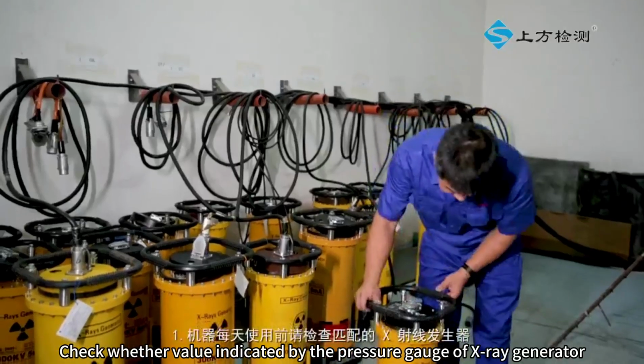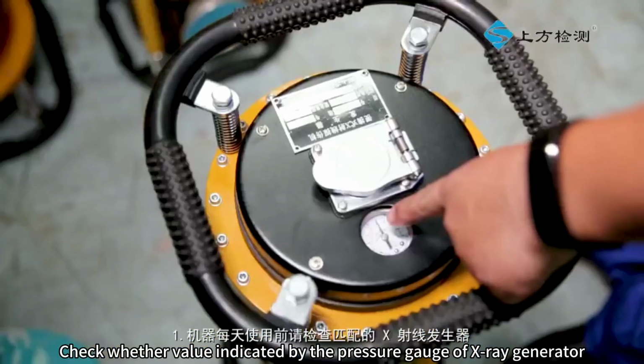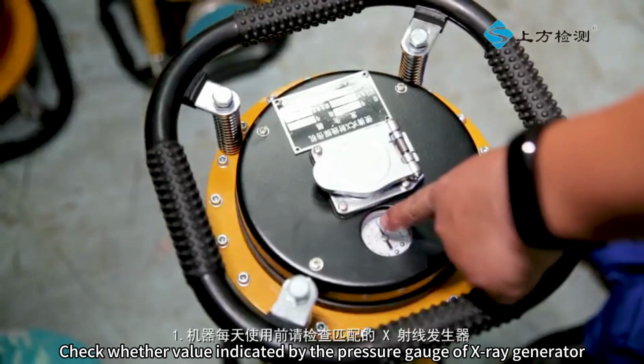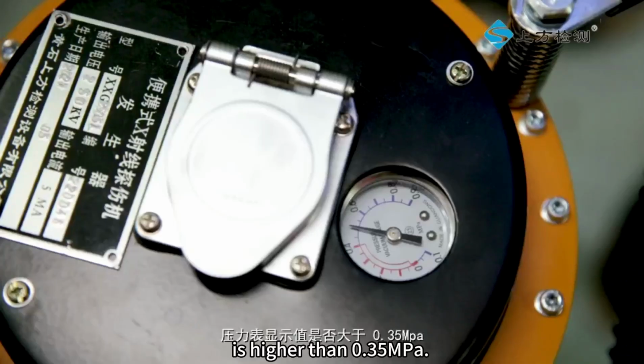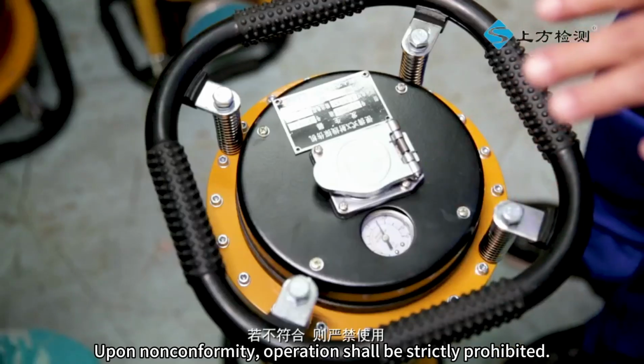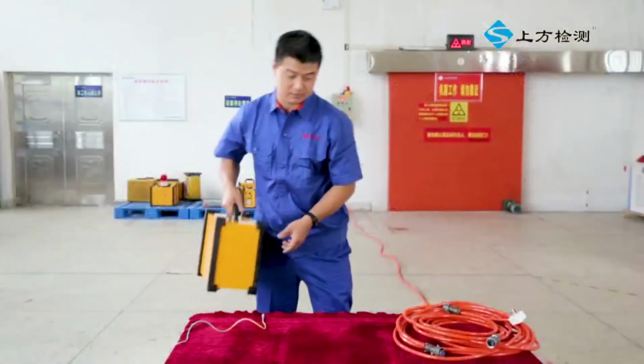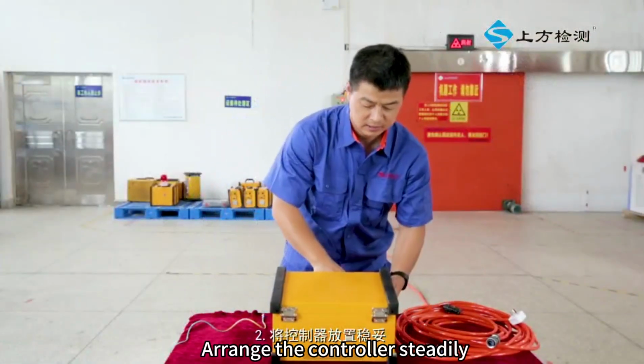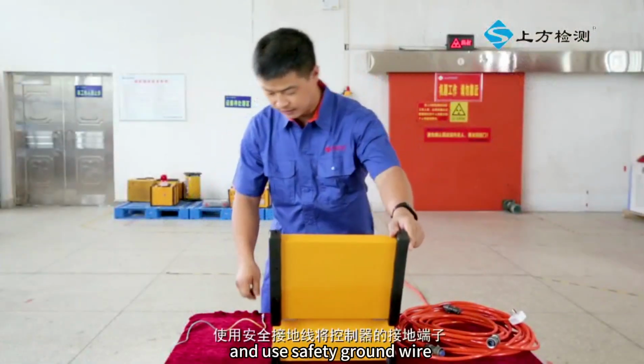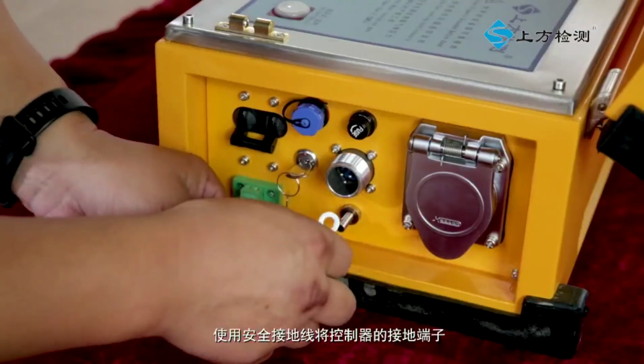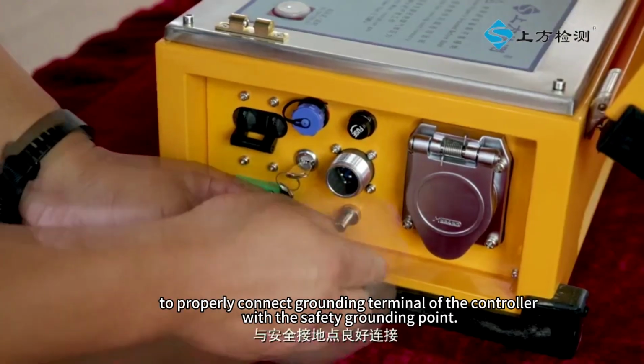Preparation before operation. Check whether the value indicated by the pressure gauge of the X-ray generator is higher than 0.35 MPa. Upon nonconformity, operation shall be strictly prohibited. Arrange the controller steadily and use the safety ground wire to properly connect the grounding terminal of the controller with the safety grounding point.